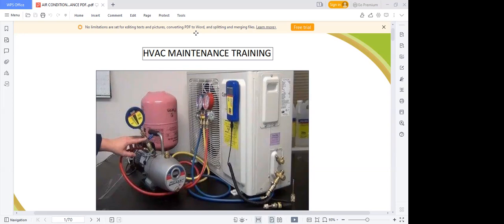Okay, so, thank you, sir. So for your maintenance, let me just give you a clue. Please, maintenance is not repair. Please, I'm begging you, maintenance is not repair. When you are doing your maintenance, what you look out for in the indoor unit is the filter, and check if your evaporator is blocked. Then your outdoor unit, you just pressure wash and make sure it is clean, and there's effective exchange of air in and out of the equipment. Then you can check your electrical cables, check your copper pipes if they are leaking. Most of the things you do are physical checks. Then you check the electrical rating going into your units. Once you have done all those, you are done with your maintenance.